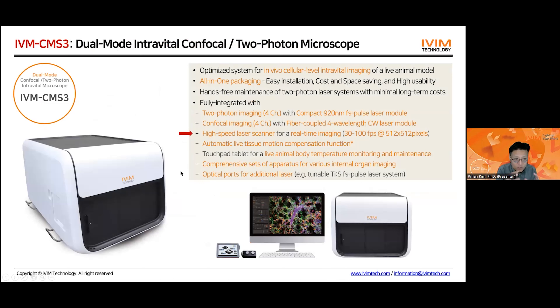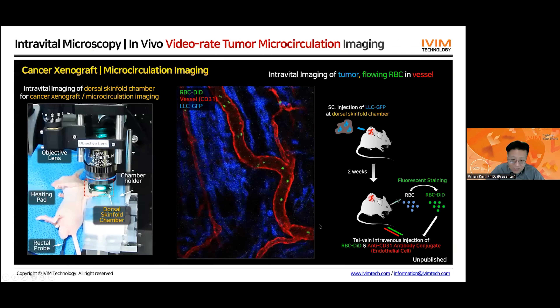A unique advantage of the CMS3 model is that it's equipped with a high-speed laser scanner for real-time imaging, capable of 30 to 100 frames per second imaging with 512 by 512 pixels. By using an ultra-fast polygonal mirror scanner, we can achieve uniform illumination over the entire imaging field of view and achieve very high speed — optionally up to 100 frames per second, though our standard system is capable of 30 frames per second. This is fast enough to visualize flowing cells, such as flowing red blood cells in the vessel over a tumor mouse model.